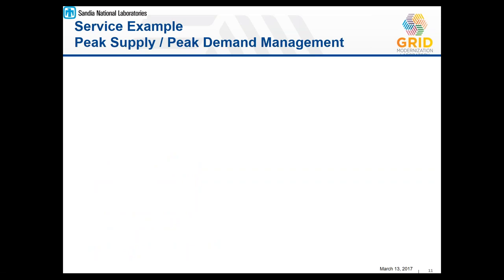Just to give a really concrete example of this, let's take the peak supply service. This can supply benefits at many different points in the grid. Say, for example, this is behind the meter. This is a commercial building of some sort that has a demand charge. And if they can reduce their maximum demand, their peak demand, over a period of a month or a year, then they can reduce that demand charge on their bill and save themselves money. Our approach for analyzing this service would be to analyze the daily peak loads for an entire year.